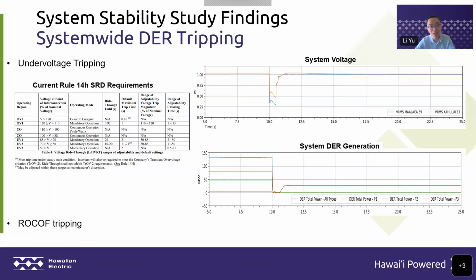And on the right-hand side, these two figures demonstrate this example. So basically, this is for the Maui system. When you have a transmission level fault lasting 0.5 seconds, that can cause more than 100 megawatts of DER tripping out of a total of around 120 or 130 megawatts of DER generation. So once we have that big generation gap, we're going to need some generation to respond immediately to that gap and stabilize the system frequency.